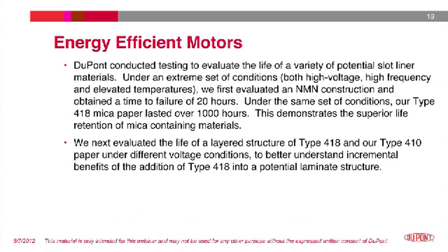Using sinusoidal voltage endurance testing, we first looked at a typical NMN laminate under a combination of corona and elevated temperatures. The testing was conducted at 360 Hz to increase the effect and obtain results in a shorter time. For the test conditions selected, the NMN lasted around 20 hours. We then evaluated using our Type 418 mica containing aramid paper under the same test conditions and obtained a lifetime of 1,000 hours. The Type 418 paper has much better resistance to partial discharge due to the mica content. However, mica-containing products tend to be quite weak mechanically.